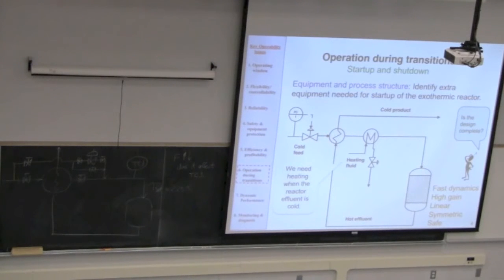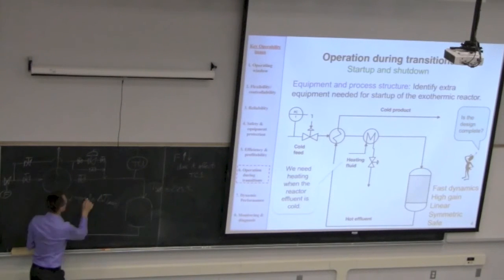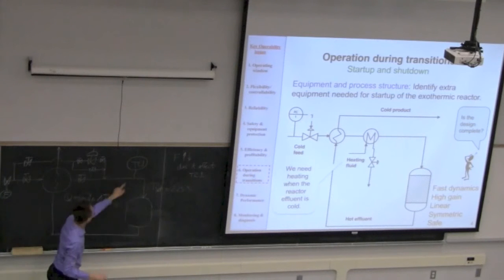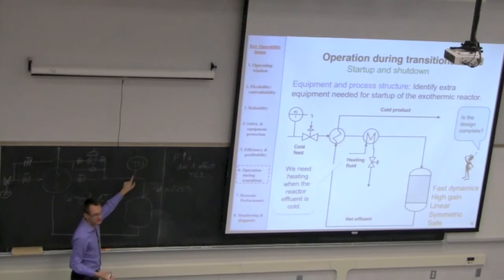I'm just considering this, but I see where it goes. So back yesterday, we had that second heating exchanger to make up the additional heat. Just talking about this loop as is, or as shown here, if I vary this flow, it's a nice idea to vary this flow because we don't have to add anything else to our process. If I vary this flow, I can manipulate this temperature. There is a cause-and-effect relationship. If you recall that in a heat exchanger, Q equals m Cp delta T, or delta T log mean, that m is the mass flow. So if that mass flow changes through this loop, so a slower flow or higher flow, I'm going to vary Q exchanged in that heat exchanger. If Q varies, Cp stays constant, delta T must change.